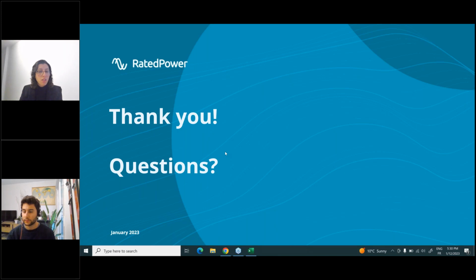One thing maybe that I didn't show in the software or directly on the interface is that if you choose a certain combination of input that would result in a bad design, you would get warnings telling you that a specific parameter, such as the voltage drop limit, is going to be exceeded, or the power loss, or something else. And we're going to suggest changing a certain input. But yes, you can design using 34.5 kilovolt. For now, we don't include four circuits. We only include two circuits, but you can choose one or two. And for the wood poles, for now, we didn't include them. We only have the steel poles or towers. But we're going to take note of this feedback. Thank you.